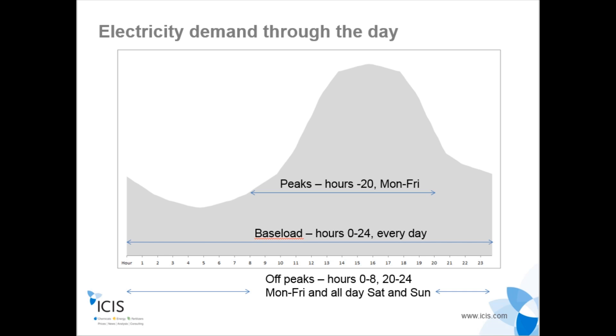As people go to sleep and electrical appliances are switched off, demand begins to fall away again. That's a basic demand curve. This brings us on to the idea of generation margins and the basic principle that power should always be generated by the means that is cheapest to do so — this is really one of the most basic ways of keeping costs down for the end user. One of the cheapest forms of power generation is nuclear power, where fuel costs and running costs are very cheap. Similarly, wind and solar have no fuel cost, so running costs are low.